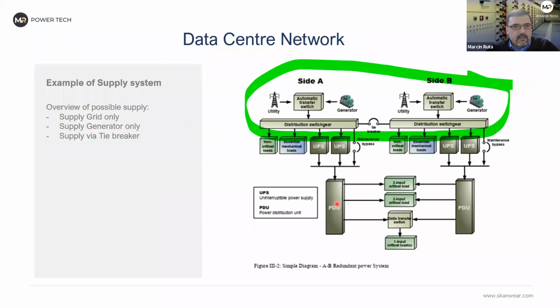So let's go. We look at the data center network. Of course, this is not a fixed configuration. It depends on the company, it depends on the project. But from our point of view, we would like to focus on the worst case scenario and actually on all of the scenarios that we can find. In this situation, just to highlight it, we can supply via grid, we can supply via generator, we can have supply via tie breakers, looking just at this area and some minimum maximum combination.